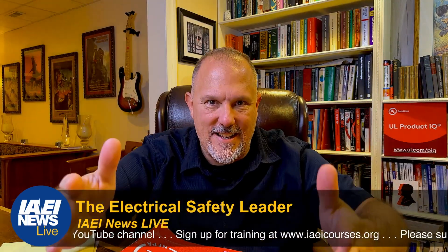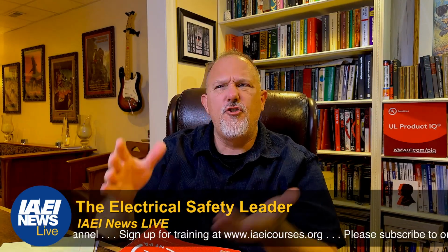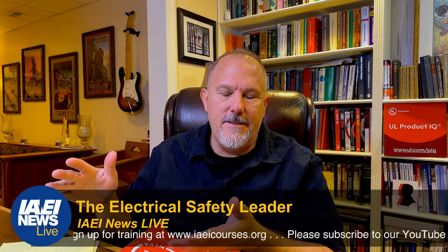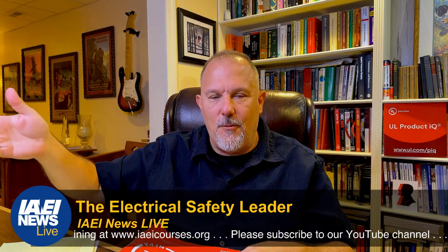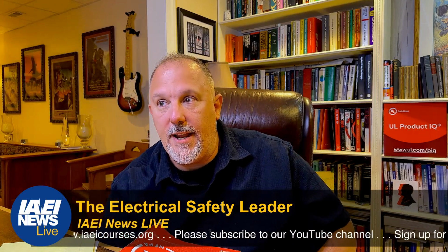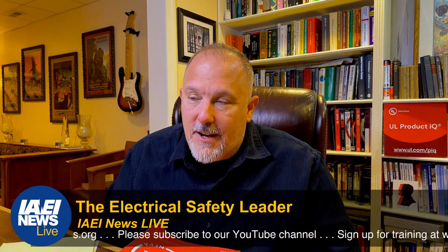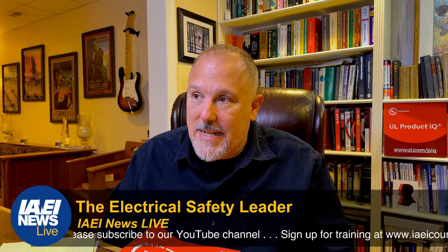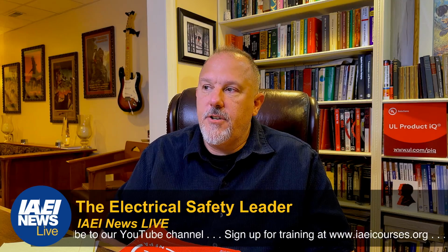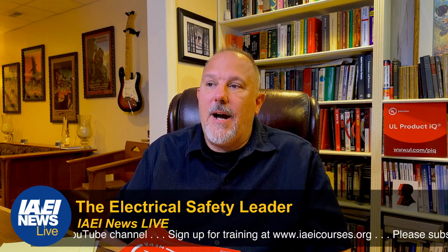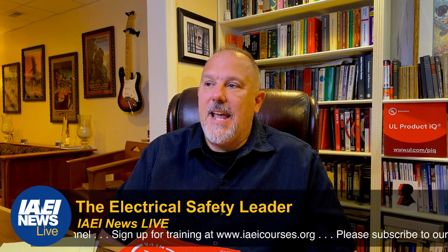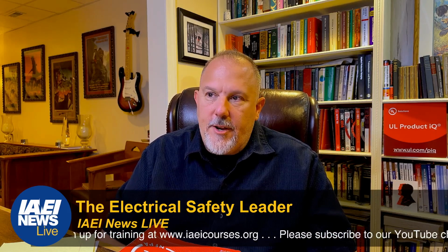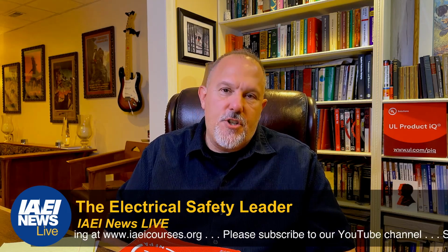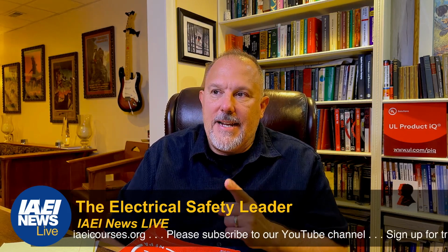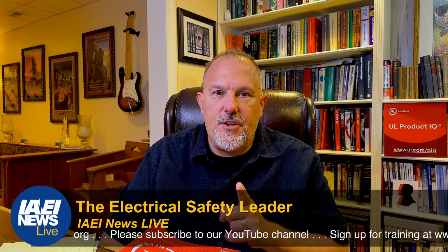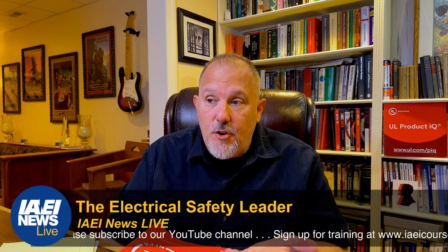Ta-da! And finally, we took the journey through the code, trying to figure out what is a surge arrestor. I took you through all of that because that's typically where we'll go, exactly that way. And then we finally get to surge arrestor rating, and we find out that it's an IEEE document, C62.11-2020, standard for metal oxide surge arresters for alternating current power circuits greater than 1 kV. And then also IEEE C62.22, guide for the application of metal oxide surge arresters for alternating current systems, for further information on surge arresters. So those two IEEE documents are available, and you'll find that in the informational note number 1 of section 242.42.